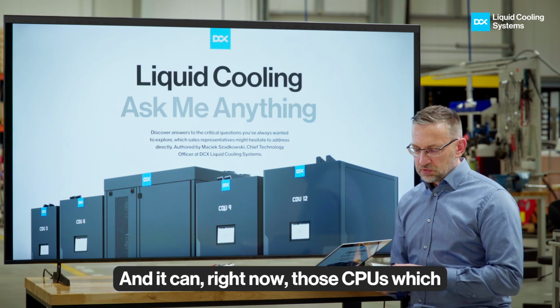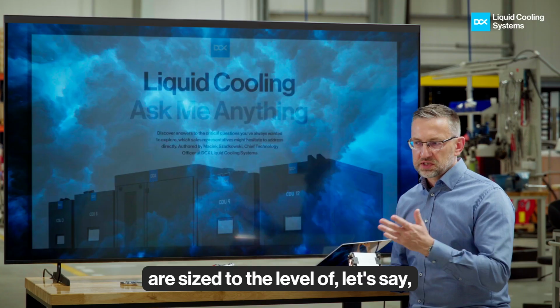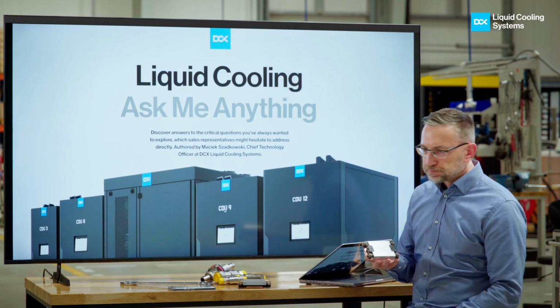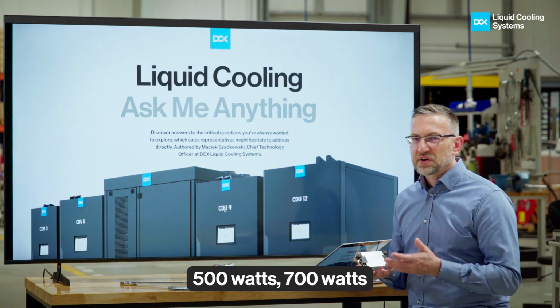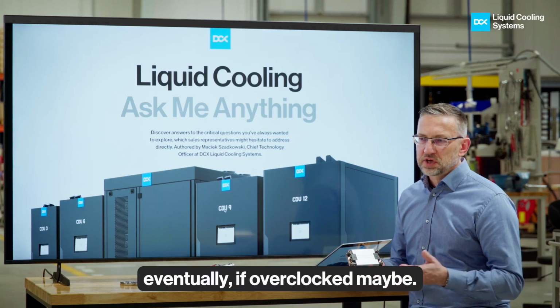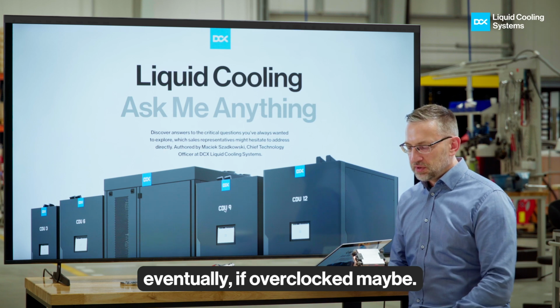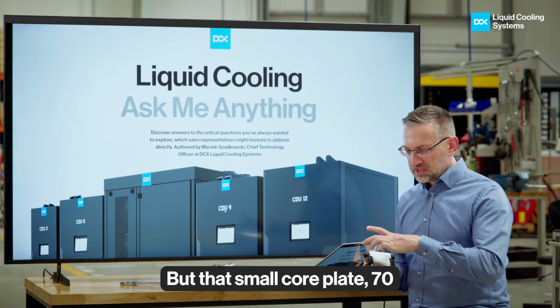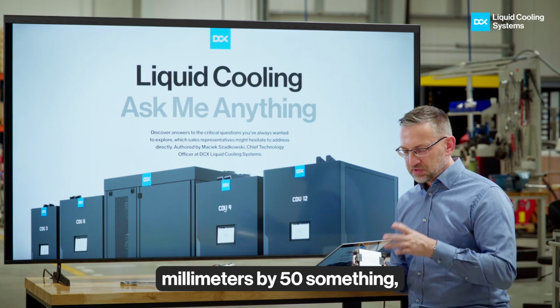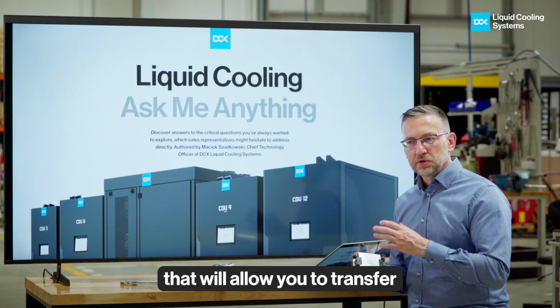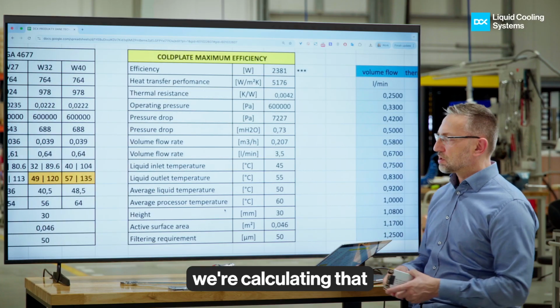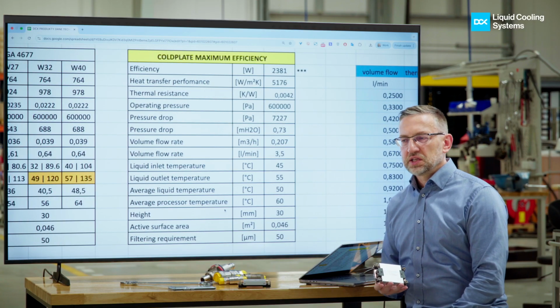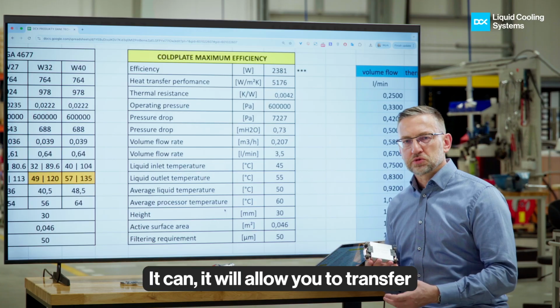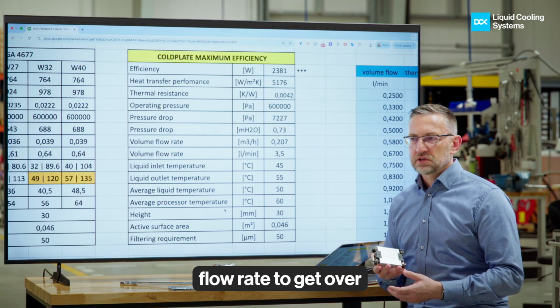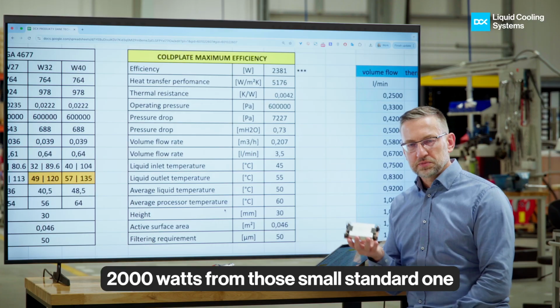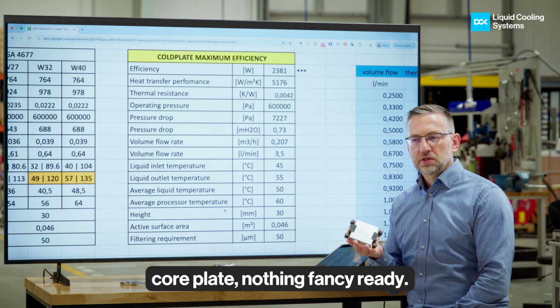Right now those CPUs are sized to around 500 to 700 watts eventually, if overclocked. But that small cold plate, about 70 by 76 by 50-something millimeters, will let you transfer, with relatively high flow rate, over 2000 watts—nothing fancy really, and we're calculating and testing this.